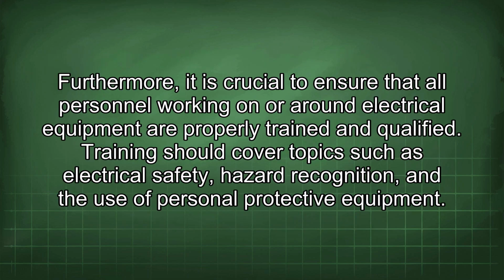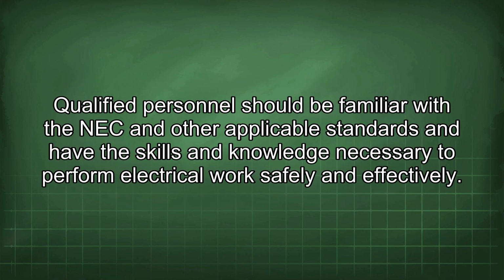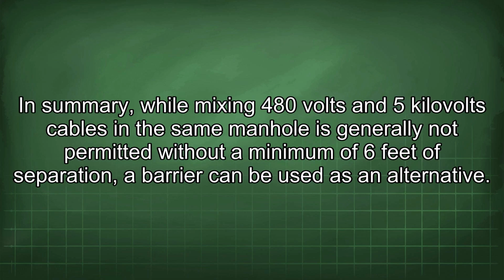Furthermore, it is crucial to ensure that all personnel working on or around electrical equipment are properly trained and qualified. Training should cover topics such as electrical safety, hazard recognition, and the use of personal protective equipment. Qualified personnel should be familiar with the NEC and other applicable standards and have the skills and knowledge necessary to perform electrical work safely and effectively. In summary, while mixing 480 volts and 5 kilovolt cables in the same manhole is generally not permitted without a minimum of 6 feet of separation, a barrier can be used as an alternative.